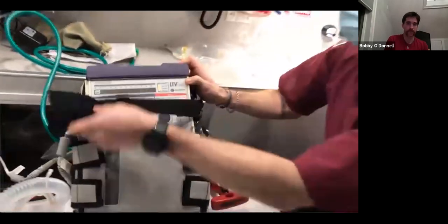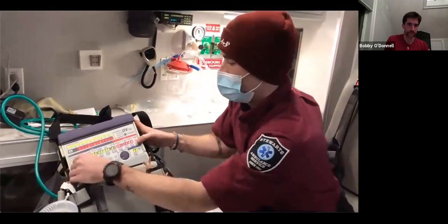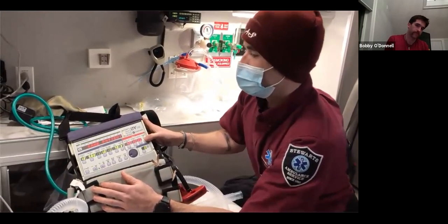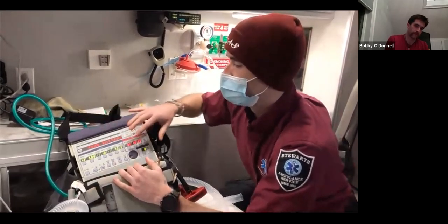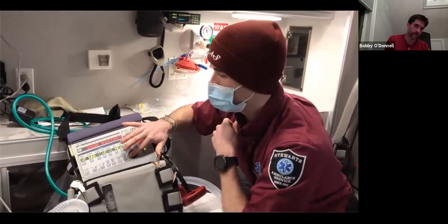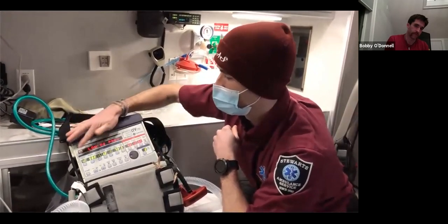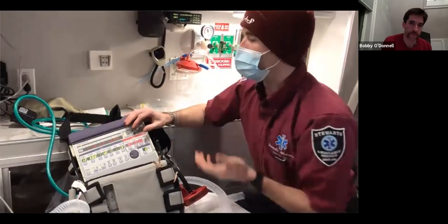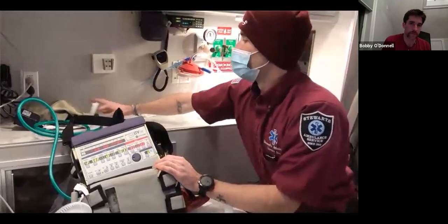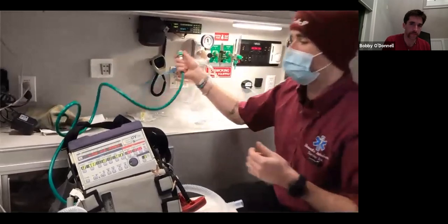So now when we turn our ventilator on, right away the most important thing to find is the silence button. And it will ask you at first if it's the same patient. So when we talk about kind of when we select things, this is our knob for changing. So we'll go to new patient, select, adult, select. It's going to be on low O2 pressure because I'm not going to connect it to oxygen because we don't want to waste the tank. But we're making sure that we're connected here and obviously going right into the wall with that quick connect.